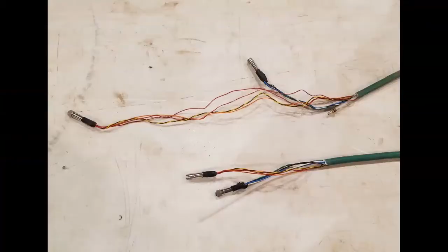Next, we will install the top end of the OI-HPT trunk line. As we look at both ends of this trunk line, you will see the exposed wire ends are different. The side with varying wire lengths connects to the probe, and the end with the equal wire lengths is the up-hole end and is the easiest to thread through the probe rods, which must lie in opposite directions, as I'm going to show. This end will also connect to the instruments.